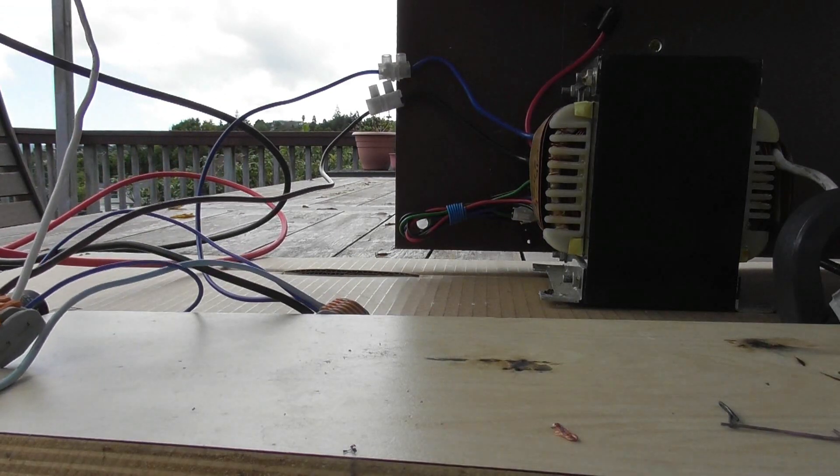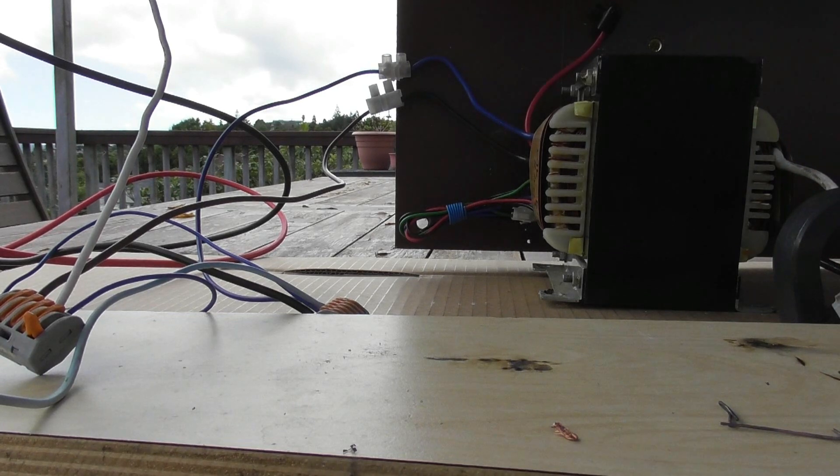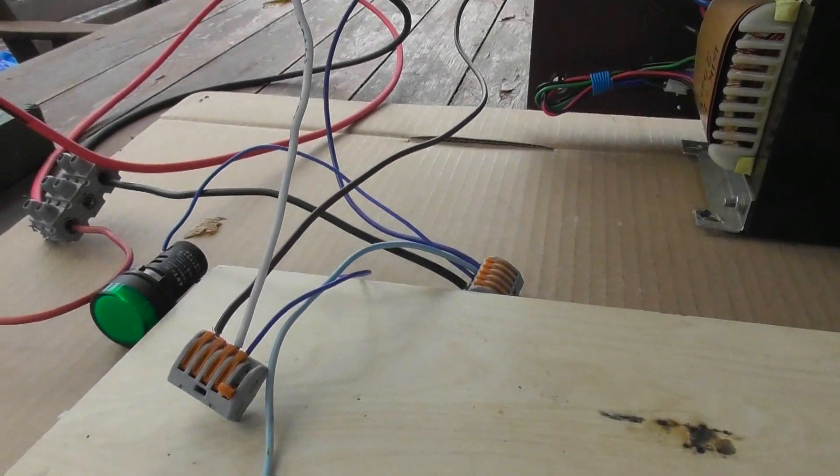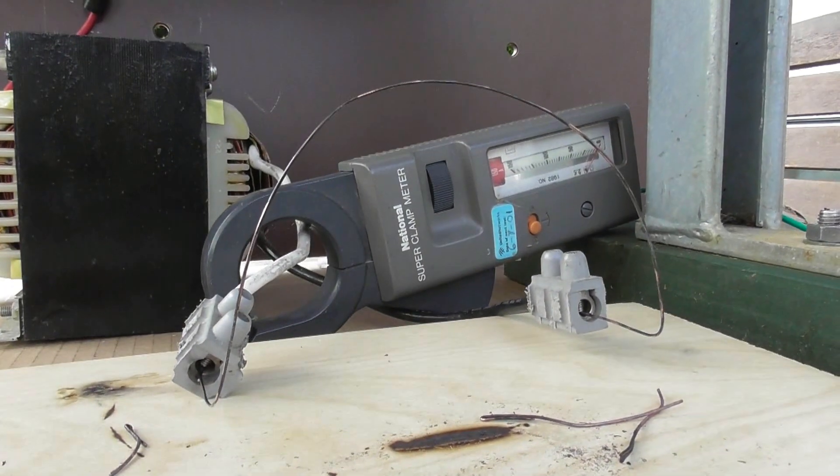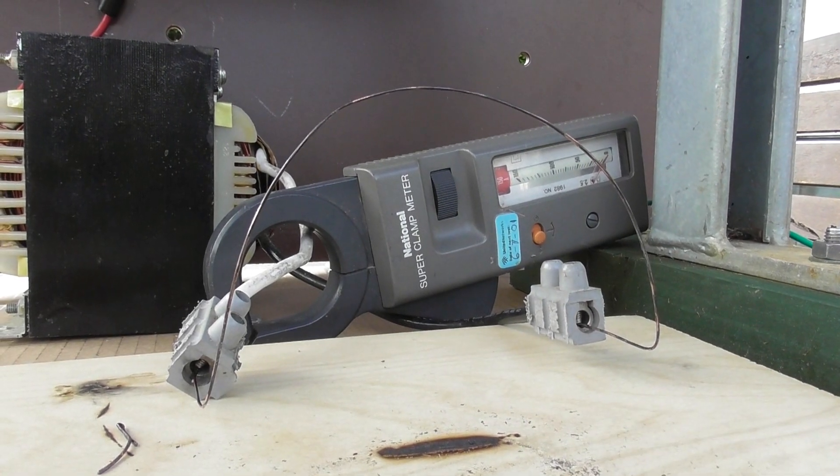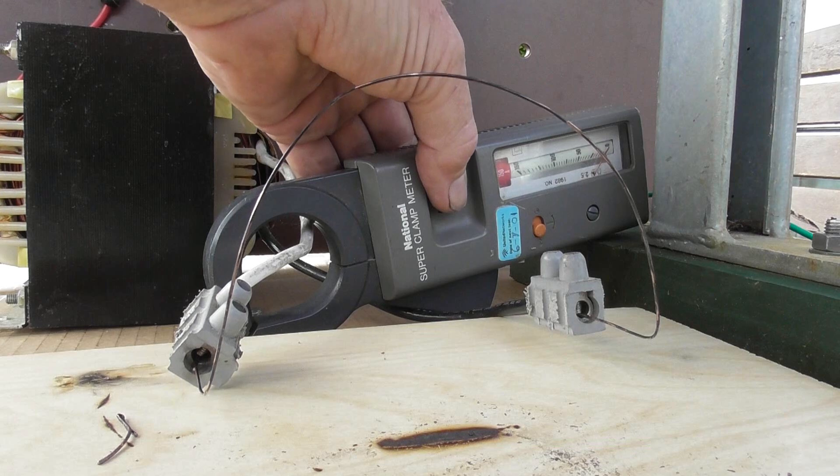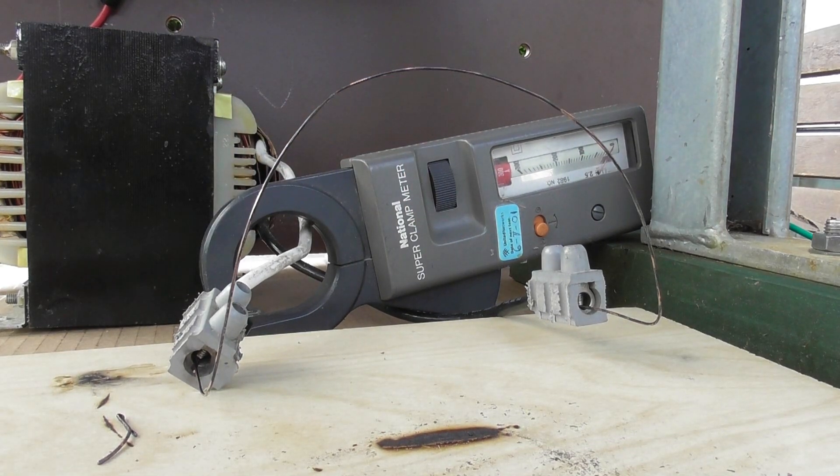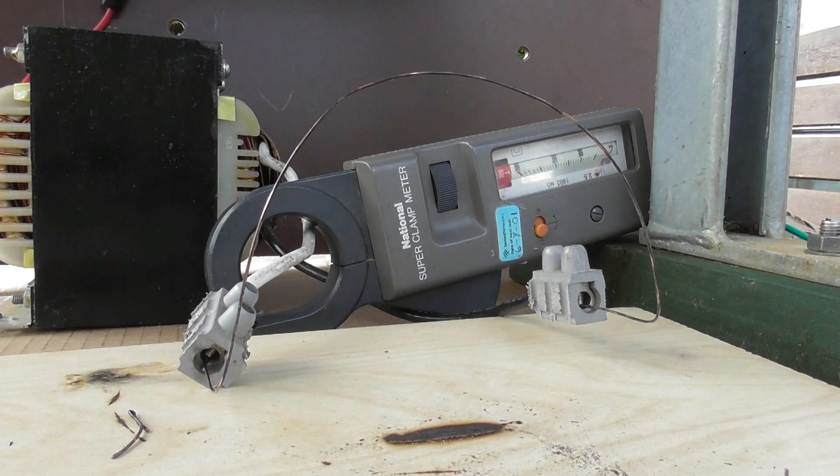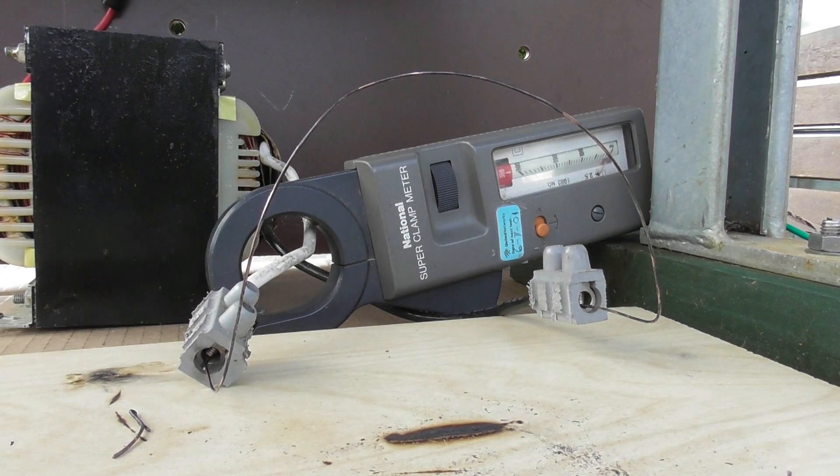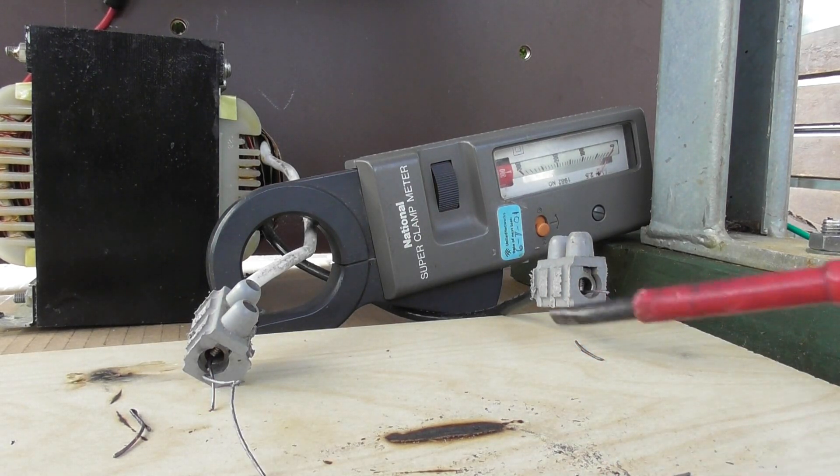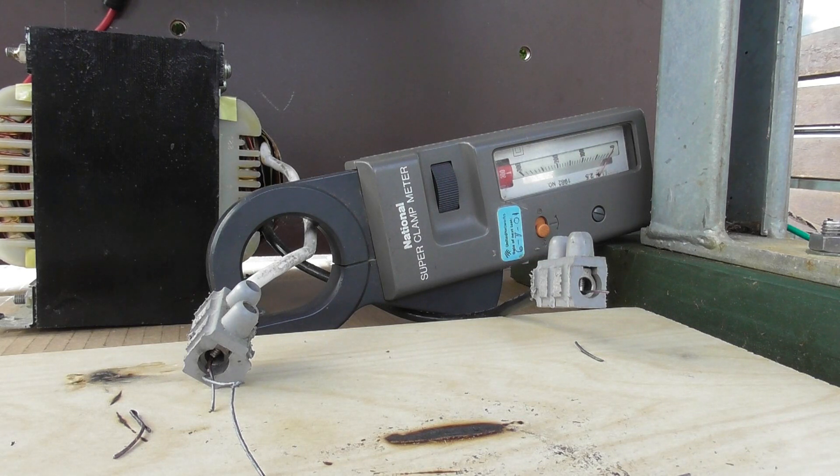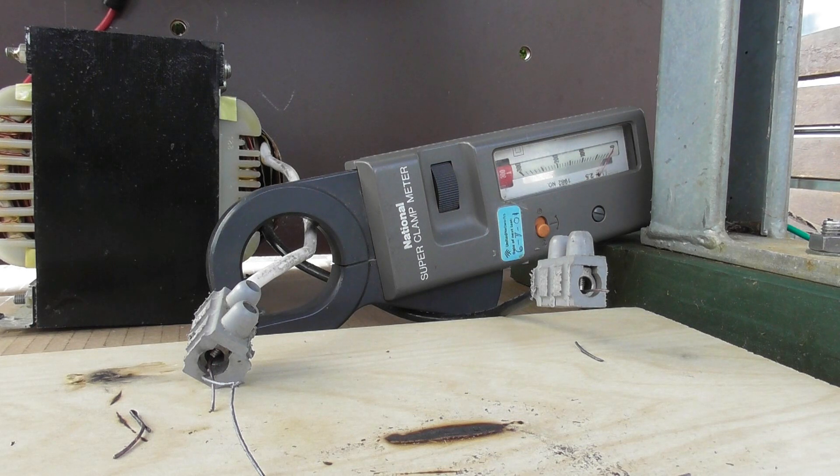I've disconnected the ballast. I'll remove it completely. And now we've got the power straight supplied to the mains, to the transformer, and straight to this same loop again. I'll put the meter on a higher scale, because I don't want to burn my meter out. I'll put it on the 300 ampere scale. And this will probably go a lot quicker. The reading here, stand by. About 150. Yeah, so this is no series inductor. De-energized device.